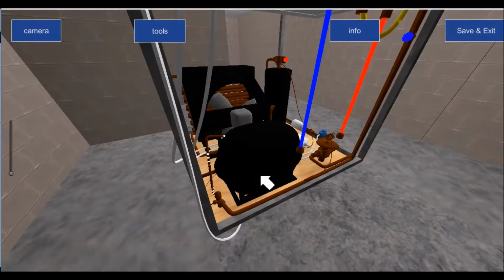A semi-hermetic compressor, on the other hand, is like a car engine. You can lift the head, you can take it pretty much apart, you can take out all of the components, such as the crankshaft, the pistons, the O-rings, the valve plate, and you can replace them all, new gaskets, all of that, and rebuild it and put it all back together. You can also change the oil in a semi-hermetic compressor, which you can't on the hermetically sealed compressor. And then you have everything from a piston type compressor to a scroll type, a centrifugal type and a screw type compressor.